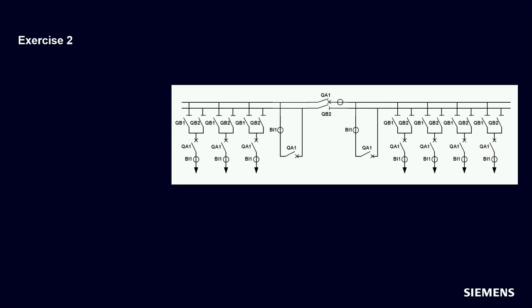Okay, now it will be interesting. How many will give the correct answers here? That's a double busbar. I see some couplers, and I see also sectionalizing couplers. I see a sectionalizing coupler. I see sectionalizing disconnectors. So first, how many bus zones do we need? I guess this hopefully is quite simple. It's 4. So 2 bus zones on the left side of the coupler and 2 bus zones on the right side of the coupler.